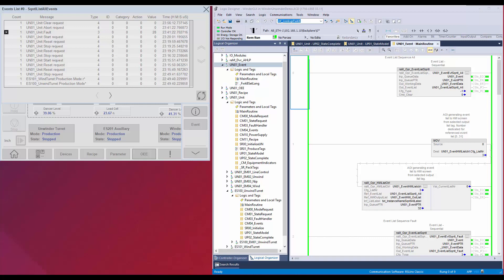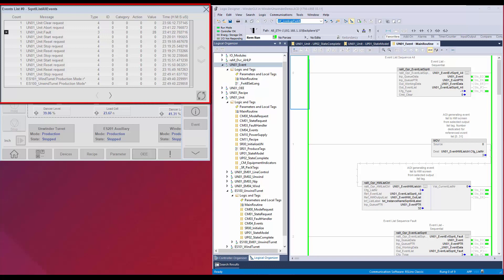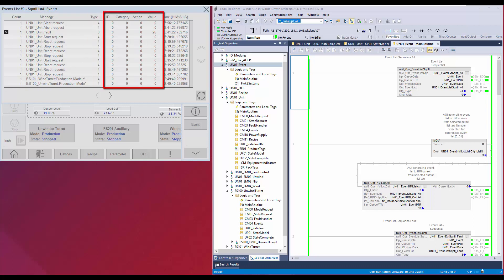Next I will demonstrate the event and language switching. This is the event program where the event queue, analytics, and language switching code resides. The event and language switching is an optional add-on and can be selected while instantiating the unit module in ACM. When selected, the unit and equipment supervisor program will come with the event routine that has event capturing code for state and mode change. It is also possible to add user events in the same event queue using the event create instruction. This is the event faceplate. The user has choice of a compact faceplate or a full faceplate. This is the full faceplate with all the details, showing event message, type as information or warning or fault, and the id, category, action, and value fields which can be used for user events.